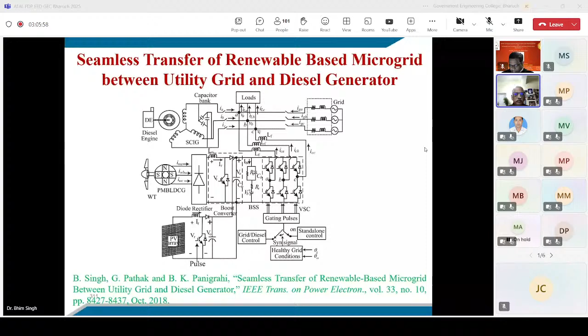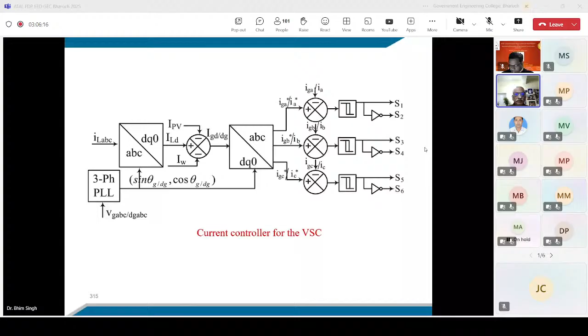This involves load compensation, voltage regulation, and angle calculation. When the angle comes closer, only then can you close the switch. These are the simulated results showing how the grid comes in and synchronization takes place, and when the grid is set.